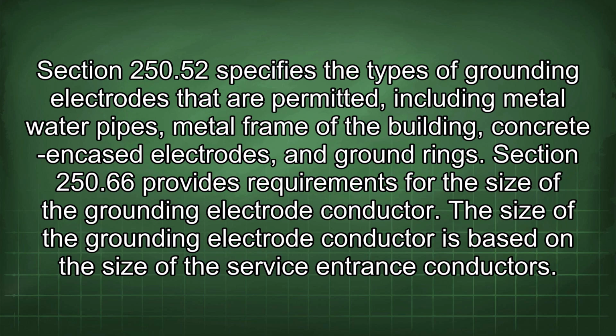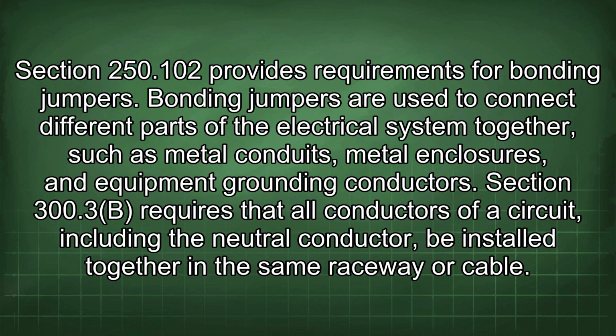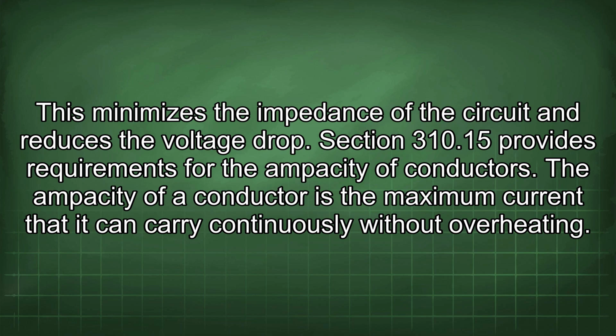Section 250.52 specifies the types of grounding electrodes that are permitted, including metal water pipes, metal frame of the building, concrete encased electrodes, and ground rings. Section 250.66 provides requirements for the size of the grounding electrode conductor. The size of the grounding electrode conductor is based on the size of the service entrance conductors. Section 250.102 provides requirements for bonding jumpers. Bonding jumpers are used to connect different parts of the electrical system together, such as metal conduits, metal enclosures, and equipment grounding conductors.